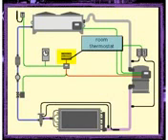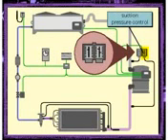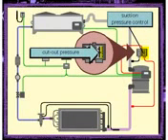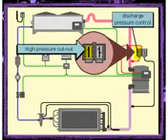The compressor can be shut off by one of the three following controls. The first is the room thermostat. This thermostat shuts off the compressor if the ambient temperature is lower than the set point temperature. The second is the pressure control that measures the minimum required pressure at the suction inlet. This means that if too little refrigerant is coming from the evaporator, the compressor will be stopped. This is the cutout pressure. And the third is the pressure control that measures the pressure at the discharge outlet. It is called the high pressure cutout. When the discharge pressure is too high, the compressor shuts down. This may indicate that there is an operating problem that could damage the mechanical components.